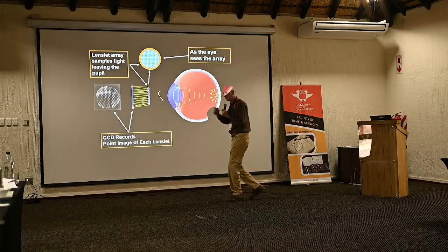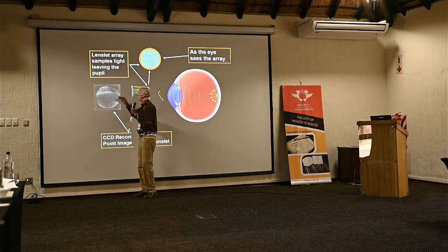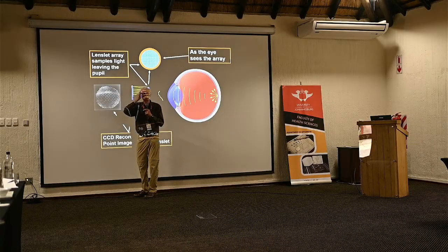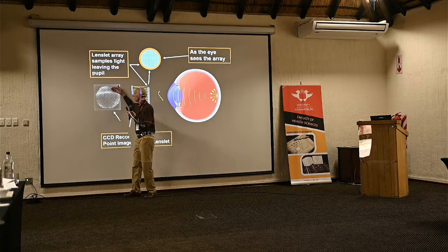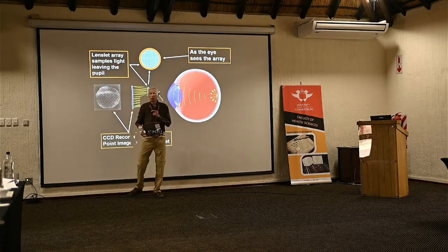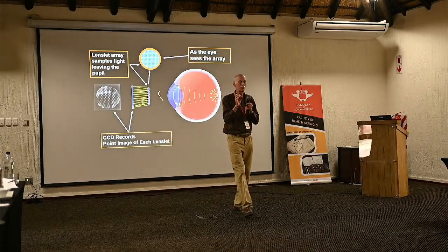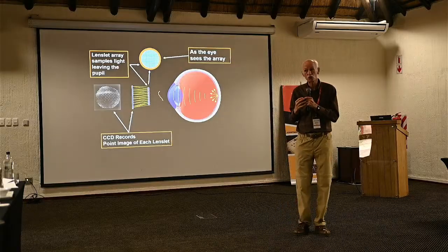Another potential mistake people made, and I've had colleagues who've had this problem, is that without special instruction that the subject should open their lids as far as possible, the lid kind of droops down a little bit, and this part is actually covered by the lid. So the pupil, when you look in, is not circular. The part of the pupil the instrument can see is a piece of a circle. It's not the whole circle.